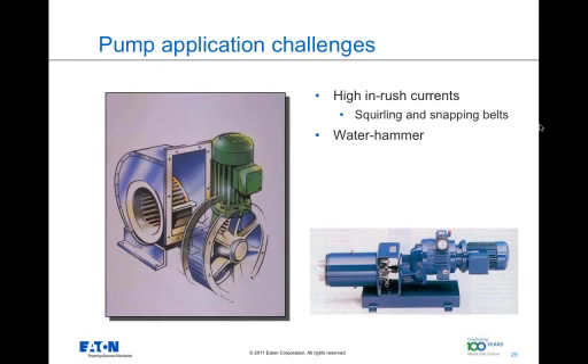Now let's get into some of the applications where soft start can give effective solutions. The first is the pump application. The typical challenges that you find in pump application are the high inrush currents causing the squirreling and snapping of belts, and the water hammer, which is a pretty common thing which happens in a pump application.